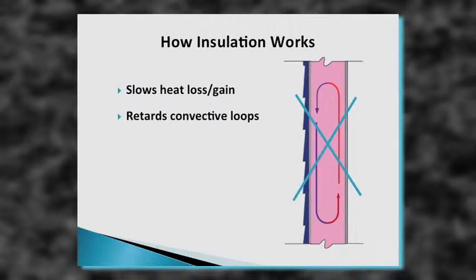Insulation works by slowing heat loss or heat gain. It also works by retarding convective loops, and it has to have an air barrier on all six sides — unless we're in the attic, in which case we need an air barrier on five sides. Think of it this way: if this room was filled with people but instead of a wall behind us there were rose bushes, the more rose bushes there were, the slower people would leave the room. Insulation works the same way — the thicker the insulation, the harder it is for heat to get through it.